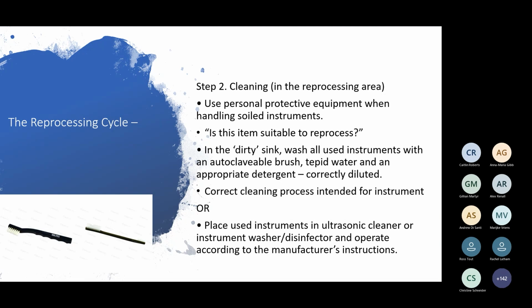So you must also do the correct cleaning process intended for instruments. So like plastics and anything with a wooden handle, there's no point putting them through an ultrasonic. They don't process in an ultrasonic. So make sure you use the correct cleaning process. And also mirrors and anything glass, please don't put them in an ultrasonic as well because they can shatter. Place used instruments in an ultrasonic cleaner or instrument washer disinfector if that's the way you're going to go and you're not just going to manually wash with a brush.